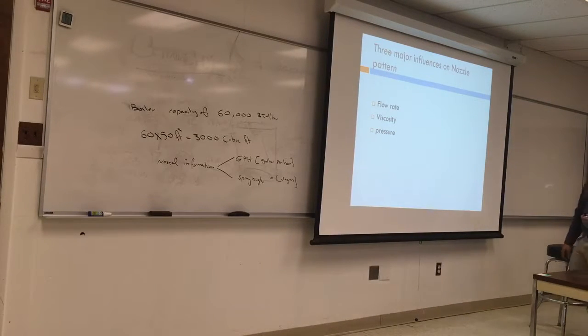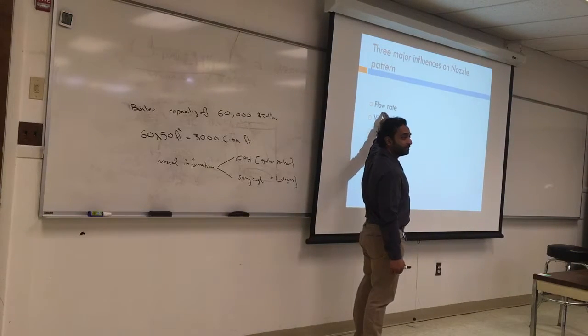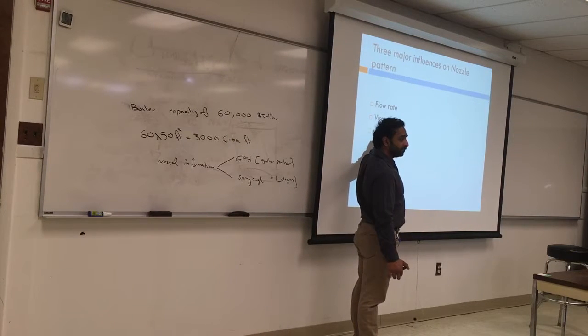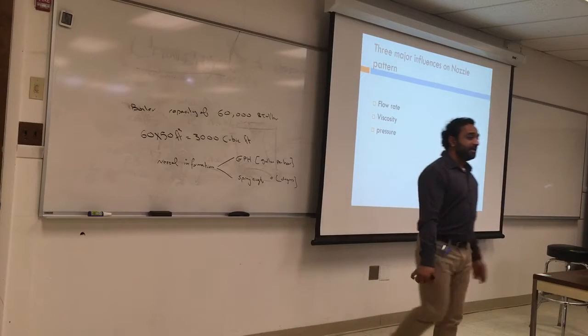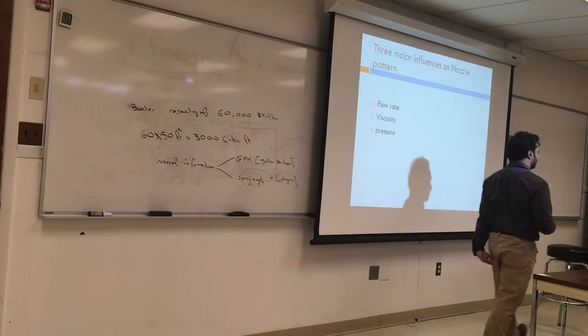So, three major factors on the nozzle pattern: the flow rate, that's gallons per hour, viscosity, which does affect the flow, and the pressure. As was said, if the oil is very cold, we should heat it and deliver the oil to the pump, and we make sure the pump is pumping to the nozzle line within specification, which is either 100 psi or 150 psi or something in between. So pressure, viscosity, and flow rate.